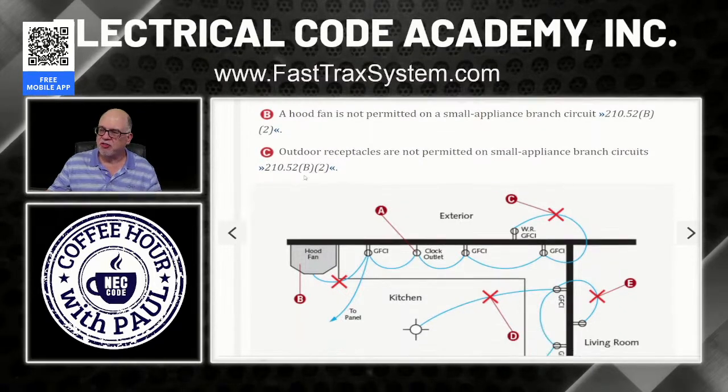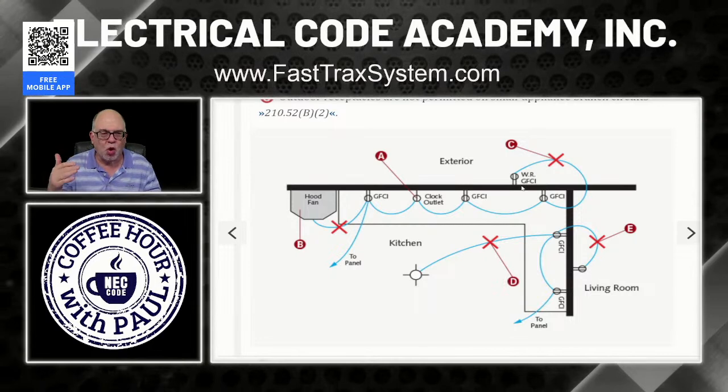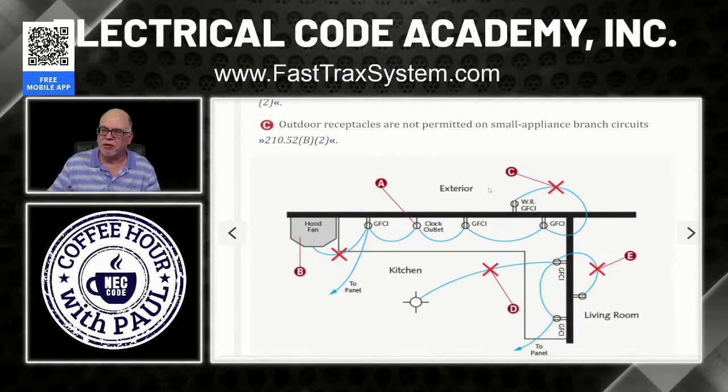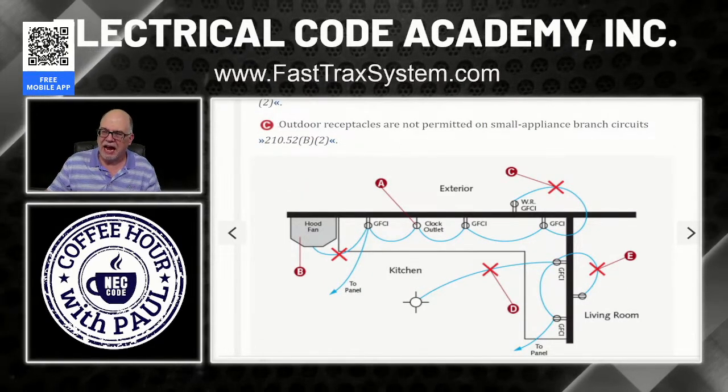All right, next, C. And look at this receptacle that's just outside. You're thinking, oh man, I have an outside receptacle. It's in that common wall. Nobody's looking. I'll just take my small appliance and drop it out there and hit that outside receptacle. Absolutely not. Outdoor receptacles are not permitted on the small appliance branch circuit. Where is that covered?